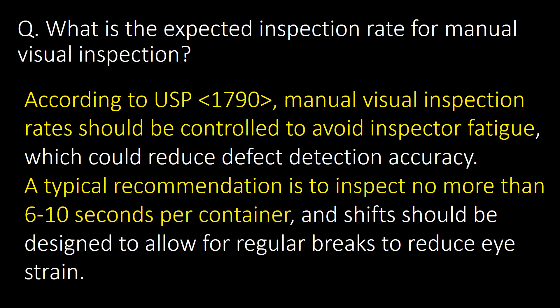What is the expected inspection rate for manual visual inspection? According to USP chapter 1790, manual visual inspection rates should be controlled to avoid inspector fatigue. A typical recommendation is to inspect no more than 6 to 10 seconds per container.